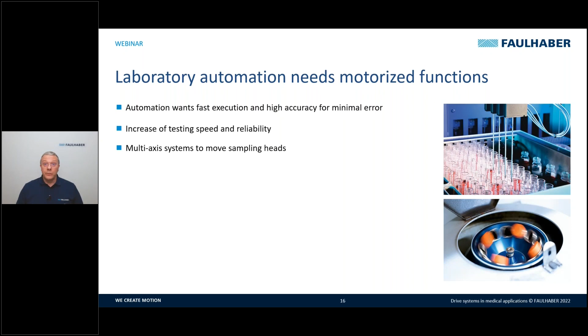This is needed to motorize the functions. High speed and high accuracy are more and more required. Increase of testing speed and increase of reliability is also a must. For this reason, we have a possibility to use our drive system for multi-axis systems to move the sampling heads like this, in order to have the highest number of tests in one machine.